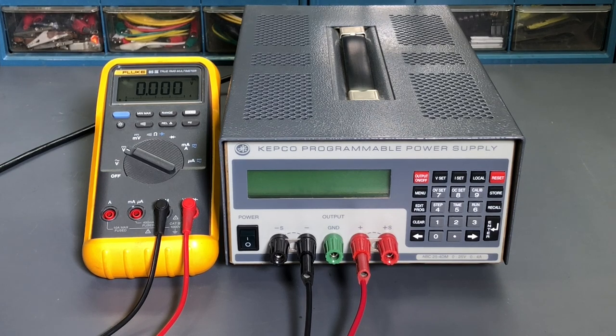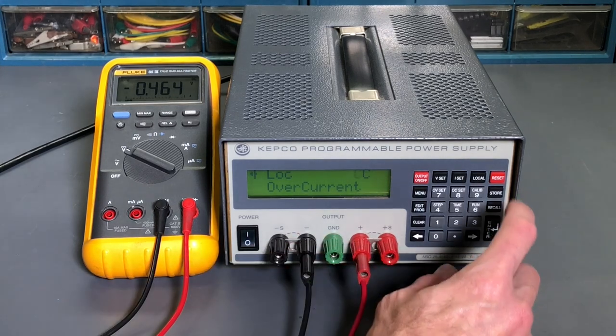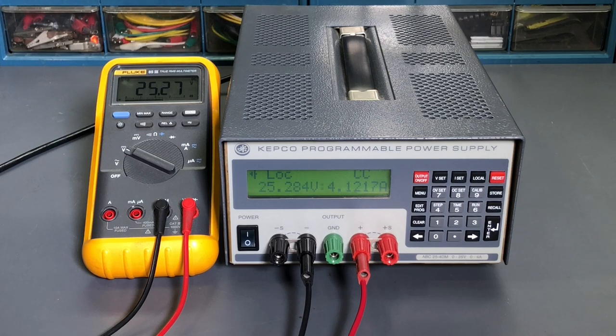I have the power cord attached to the Kepco ABC 25-4DM, and my Fluke 85 III digital multimeter is connected to the front panel binding posts to monitor the output voltage. Let's turn the power on. It does a quick self-test — the internal memory passes. Then we can see a definite problem: it says over current and there is no load connected, these leads are just going to my digital multimeter. It's toggling between constant current and constant voltage. The LOC in the upper left corner just means local control, so that's normal. The digital multimeter is indicating negative 0.464 volts. If I hit reset, it jumps to over 25 volt output — 25.27 — with a lot of jumping around on the voltage and current display. That's definitely not right.